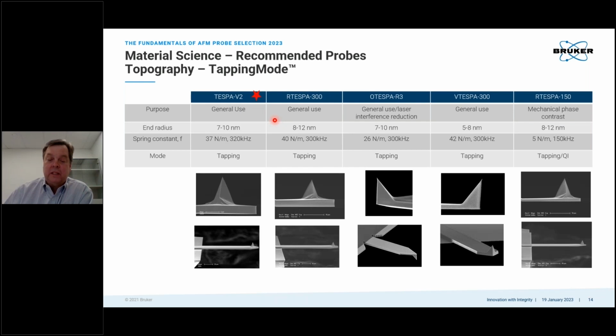All of these probes, except for the last one on the right, are 300 kilohertz probes. They're general silicon etched probes. They'll have slightly different geometries though. The TESP, like I said, was one of the first ones, but if you put it in the tip holder, it tilts it, and the back side's 90 degrees and the front side's 35. So for that reason, we came up with this R-TESPA, and you can almost see the difference slightly. You have the short side of the etching over here on the TESP, and this is reversed on the R-TESPA. Otherwise, they're very similar. They're both very good probes.